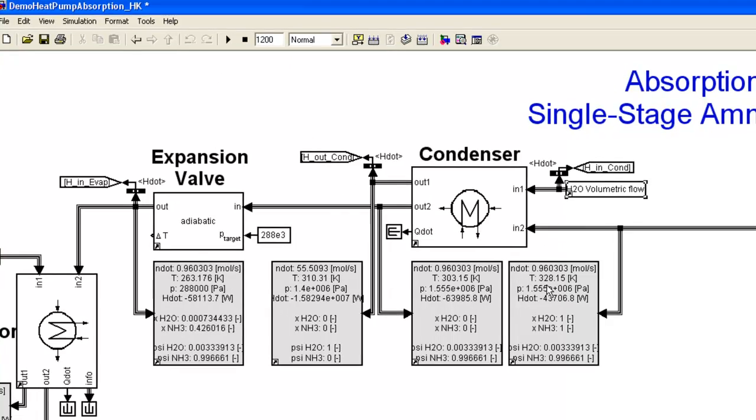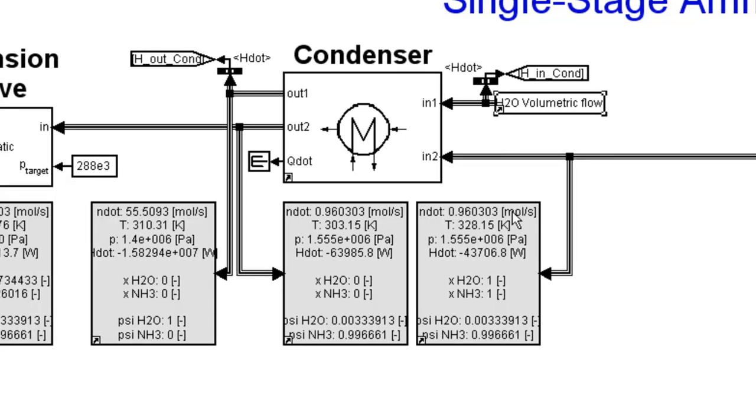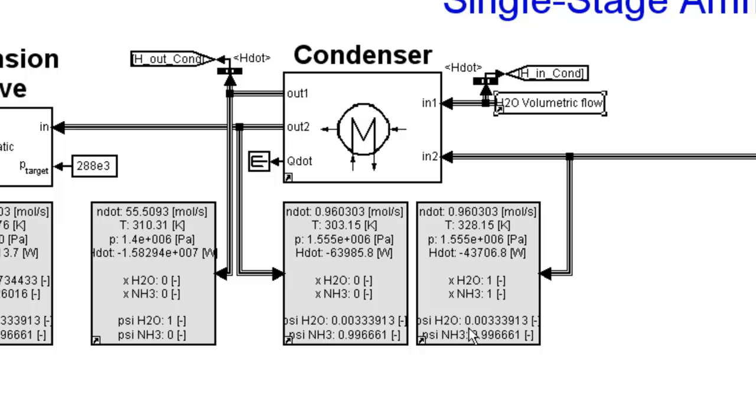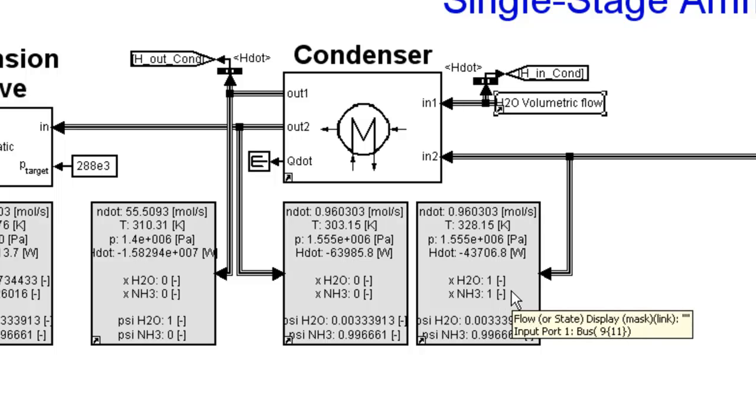If we look at the first flow display, this is the hot ammonia gas that's going through the condenser. It's going at a percentage of 99% ammonia in the solution. It has a temperature of 328 Kelvin and it's mostly gas. Actually, it's 100% gas. How do I know that? By looking at this XNH3, which says that it's 100% gas.